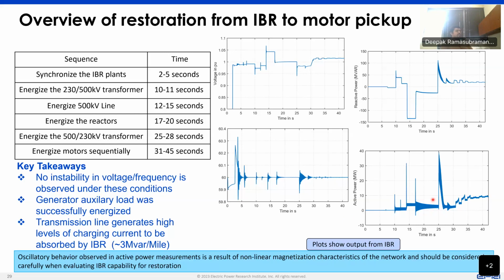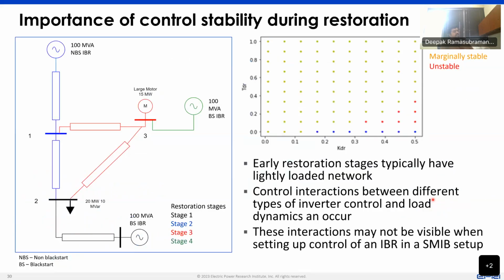Now, a way this can be done, a methodology to try to understand some of the impacts of these characteristics of the network and their potential for having instability, is looking at some kind of a stability analysis during a black start scenario. So consider that you have multiple stages of restoration. Stage 1 restoration is just looking at this one particular plant that you want to black start and a particular line and pick up some local load. Stage 2 would be to go from here and pick up another inverter-based resource and bring that online. Stage 3 will be to go and pick up some motor load, and stage 4 would be to pick up a second inverter-based resource that can come in and help the entire network.